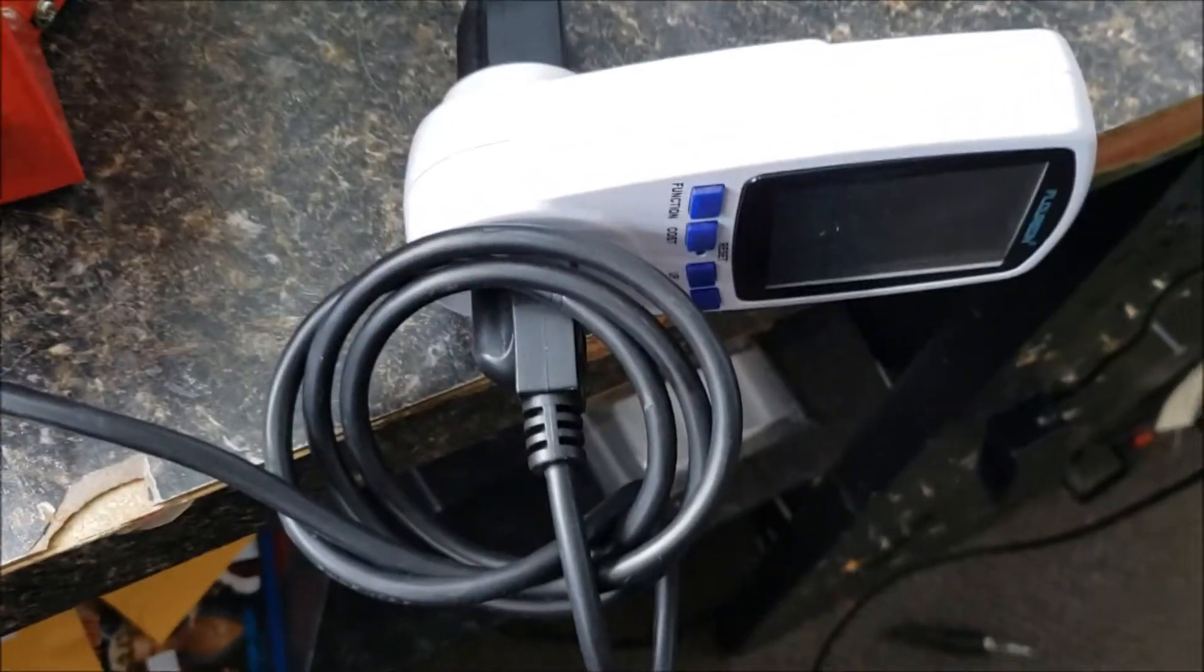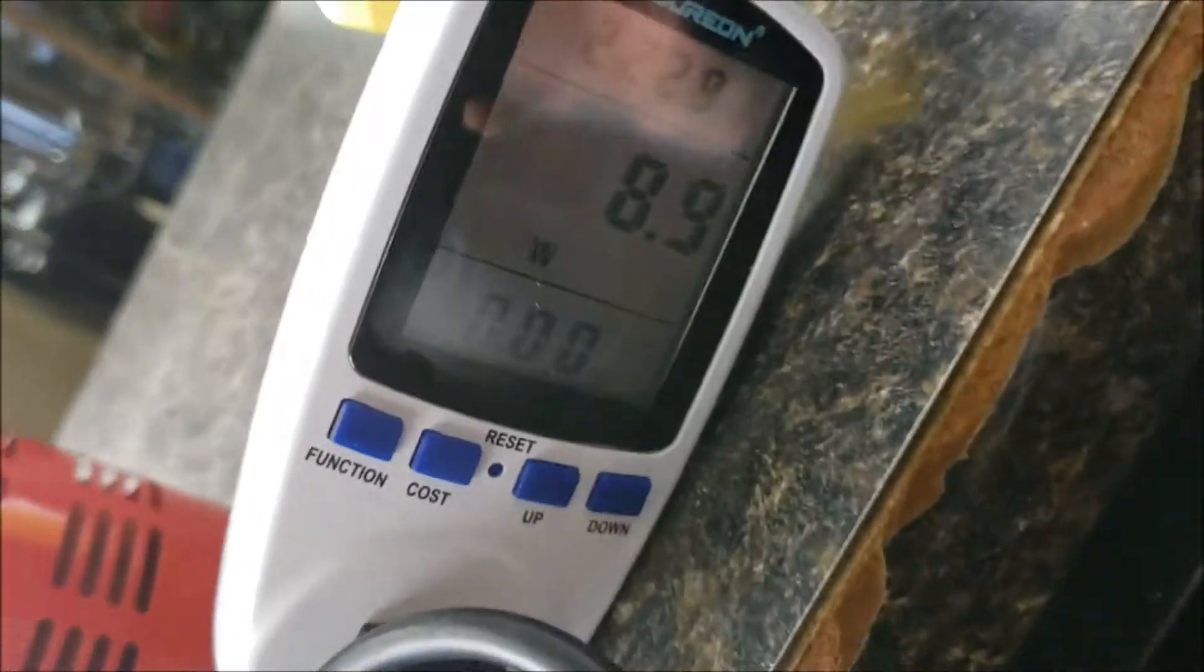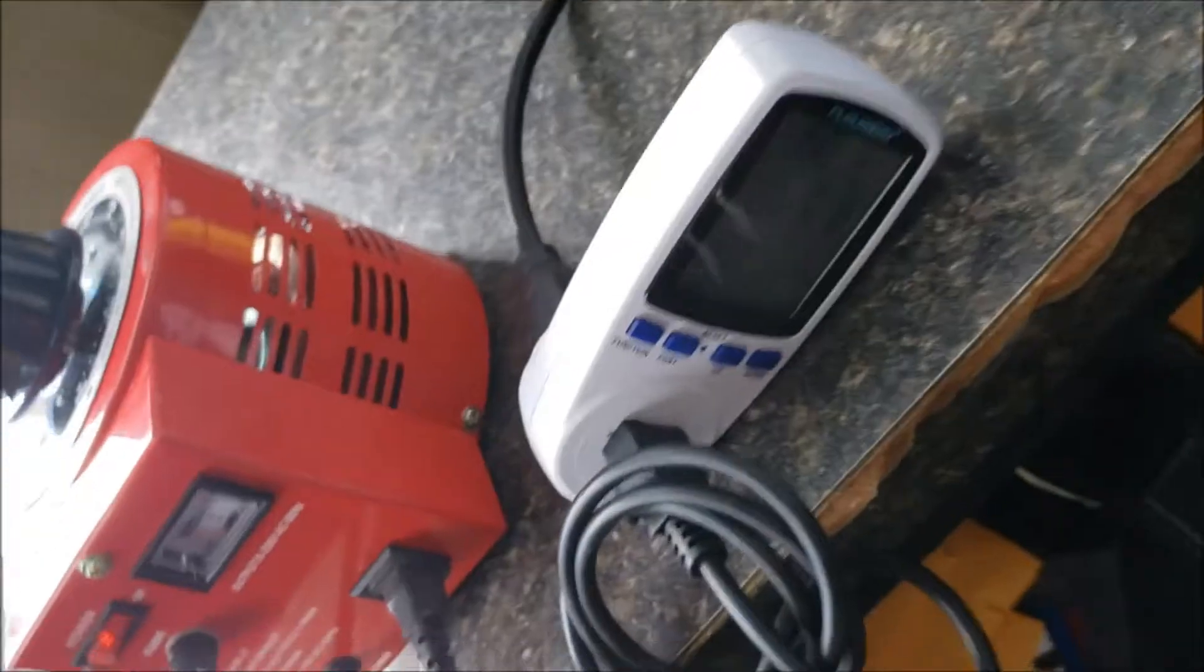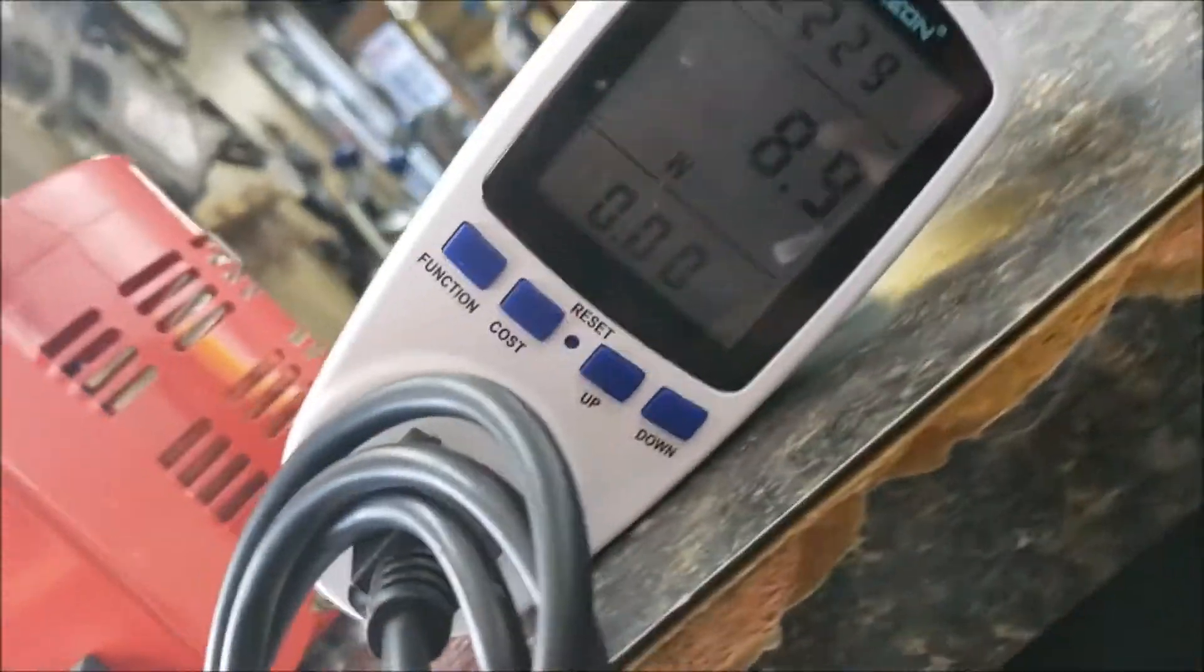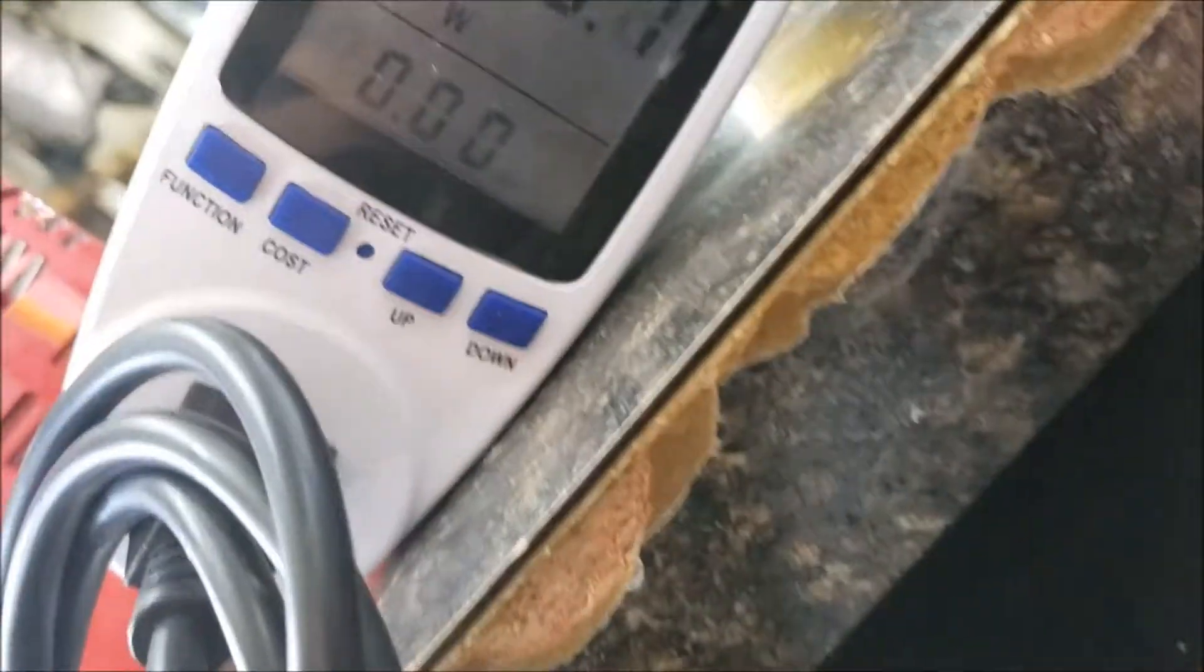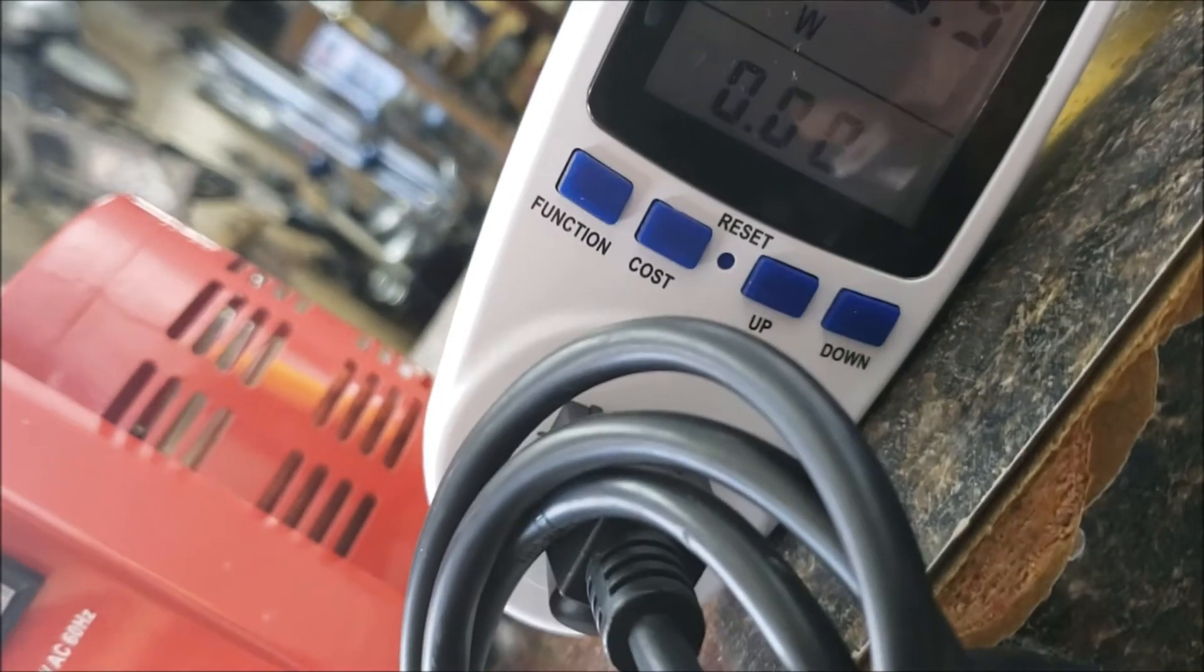If I turn the system on, you'll see the cryo-cooler is working. You want to see the wattage, and only the wattage that you can see on this meter, that goes up as you turn the Variac up.